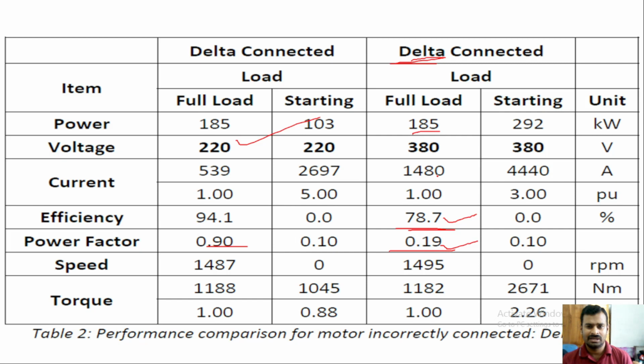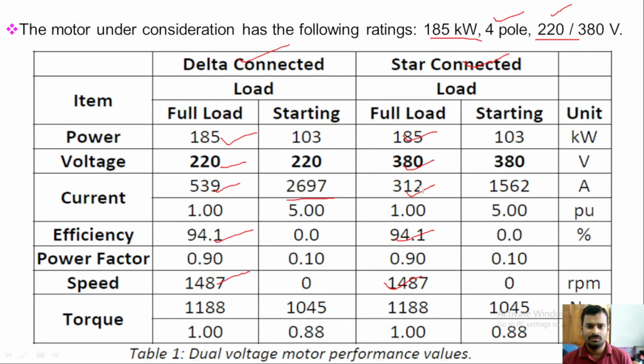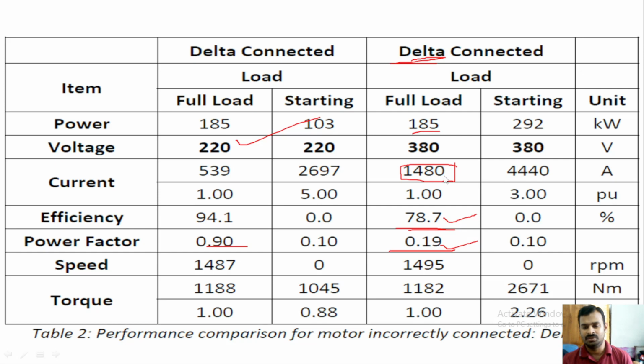And also you can see the current. This is a very important thing. When we connect it in star connection, you get almost 312 amperes of current. But now what happens? It is 1480. That means it is almost 500% of the normal expected current. So in a star connection you get almost 300 plus, but here in delta connection you get 1500. So it is almost 5 times the expected current. It is going to damage the coil and the insulation, and if your overload relay and the protective mechanisms are working well, it may trip, so it will not allow the motor to run. In case the OLR and the protective devices are not functioning appropriately, then it may damage the motor.